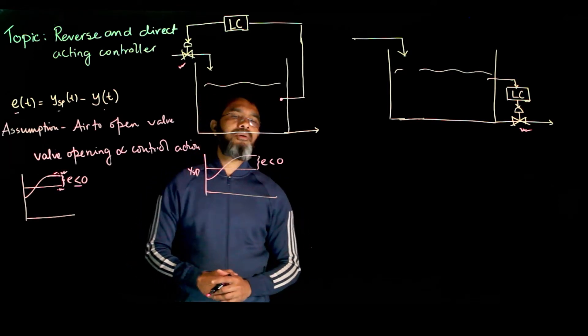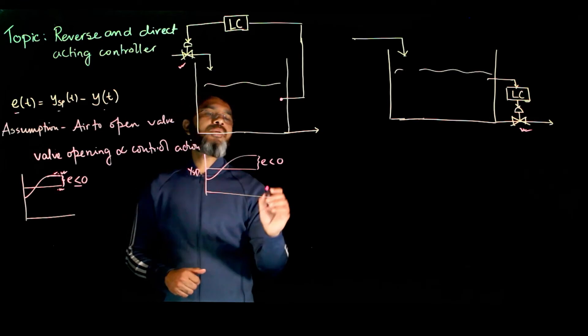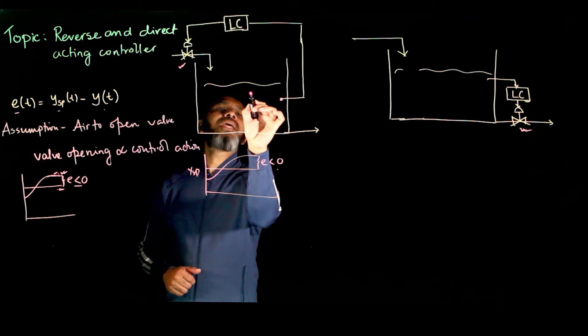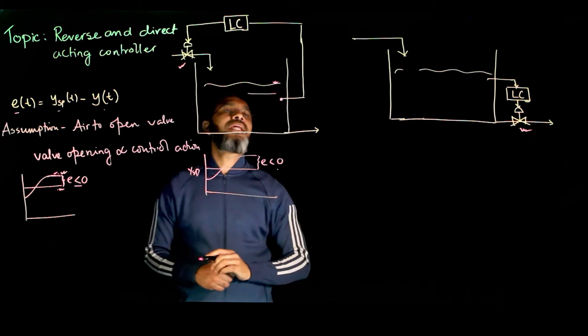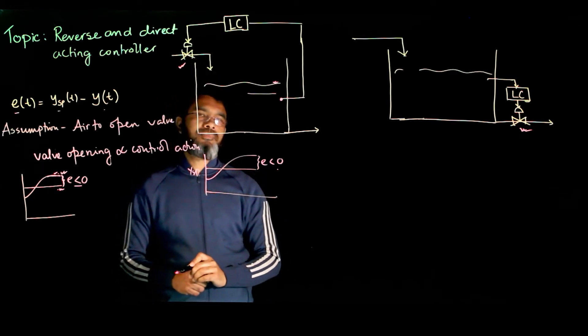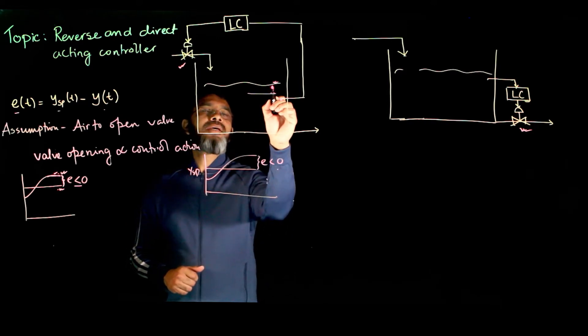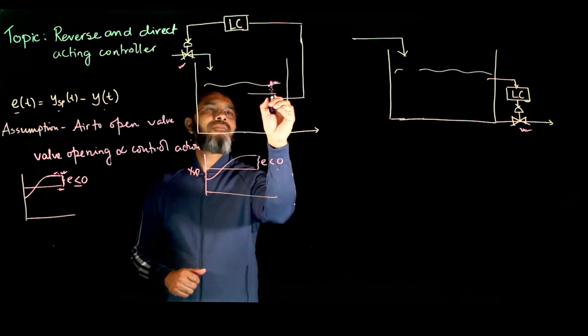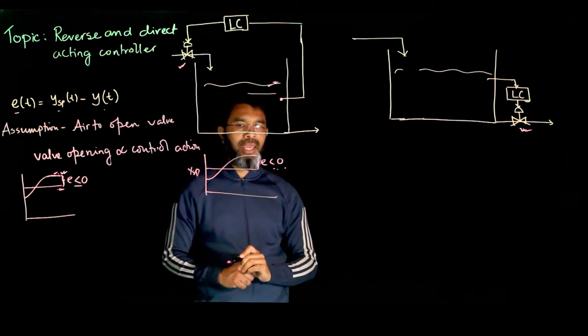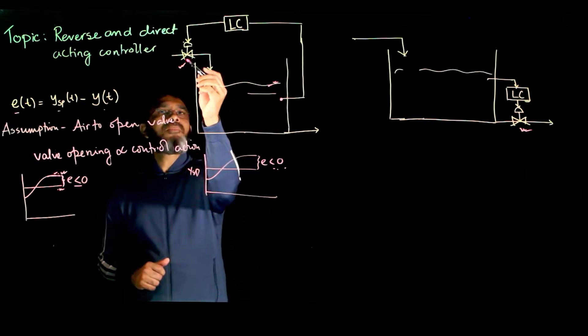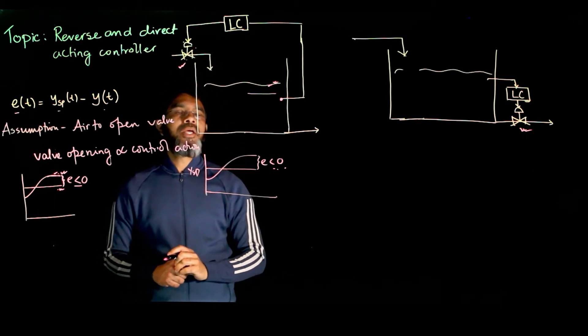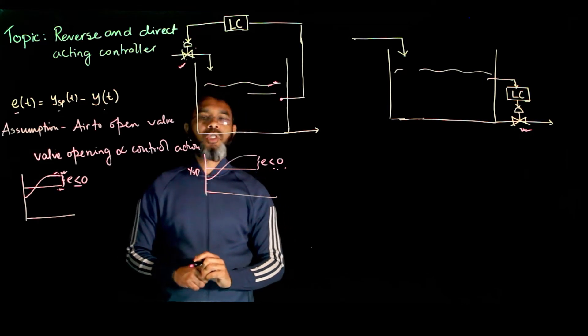More control action means more valve opening. When the error is negative — meaning the current value exceeds the desired value — you need to close this valve. Since more control action opens the valve, to close the valve you need to reduce the control action.